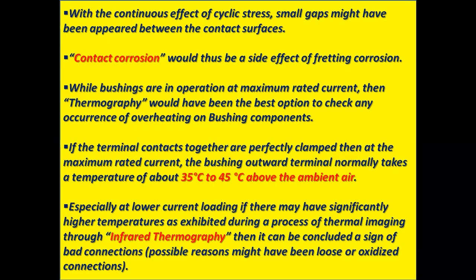While bushings are in operation at maximum rated current, thermography would be the best option to check for the occurrence of overheating on bushing components. If the terminal contacts are perfectly clamped, then at the maximum rated current, the bushing outward terminal normally takes a temperature of about 35 degrees centigrade to 45 degrees centigrade above the ambient air.